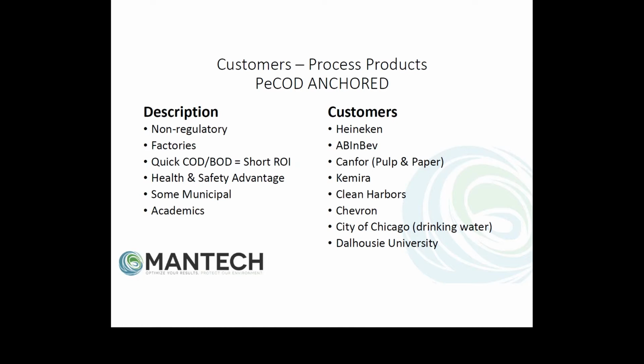For example, we have a gas refinery where it's $100,000 a quarter in additional profit since investing in the PeCOD. A secondary, very important advantage, often non-financial, is health and safety. Just the fact of eliminating chromium, mercury, and concentrated sulfuric acid, as well as the high temperatures from operations, and bringing in the green chemistry PeCOD improves the health and safety of the operators, engineers, and analysts in the factory or municipal plant, while protecting the environment at the same time. It's a triple bottom line effect in investing in MANTECH analyzers.